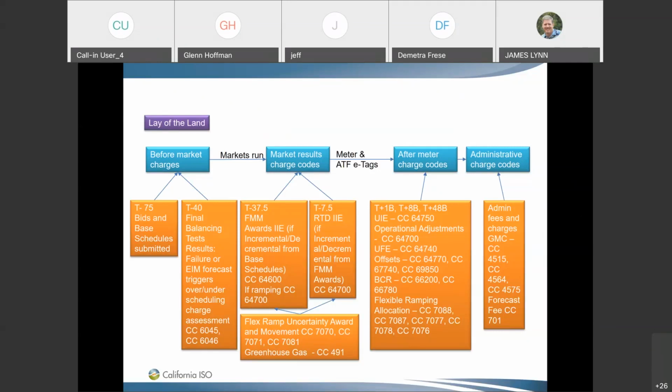And again, I hope you guys caught what I said a second ago, which was being eligible to receive payments or compensation for other balancing authority areas leaning on you. You have to have not failed this balancing test at all for the entire day.